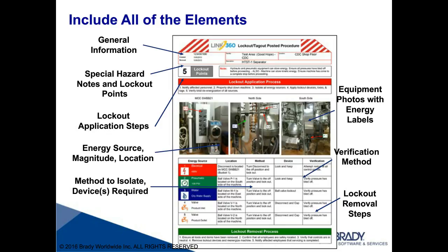When energy sources are entered, it accumulates them to count the lockout points. Then there's a note section, which some customers change to a caution section, something not necessarily related to lockout tagout but with unique hazards specific to that machine that the person doing the work would want to know about.